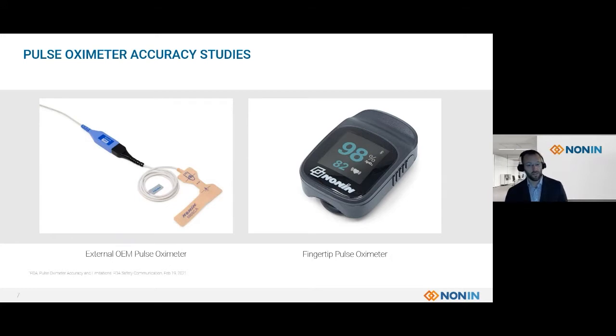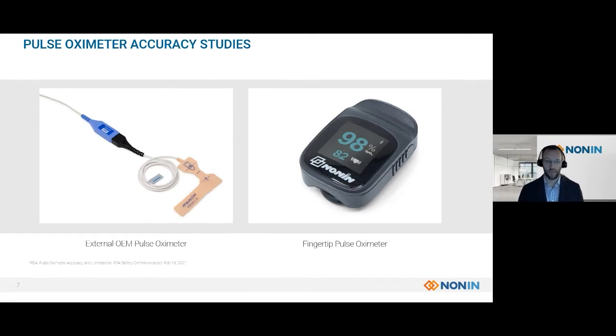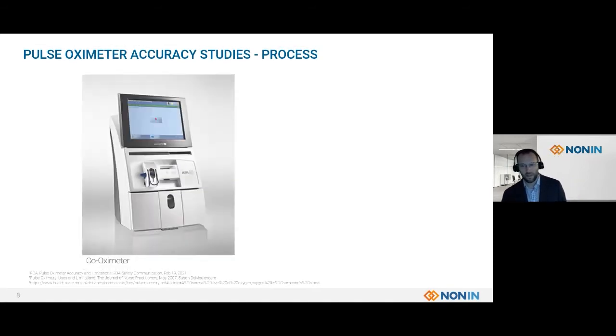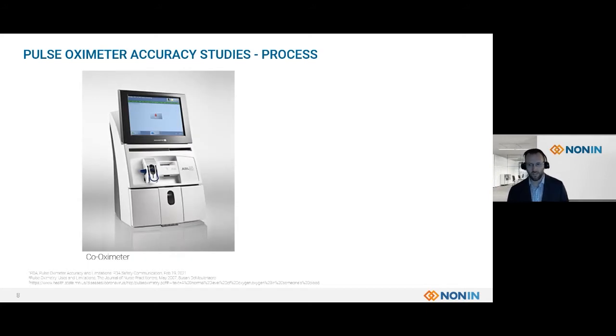These are the two types of our pulse oximeters, and both of these have gone through the same level of testing. So let's see about a pulse oximetry study. The true gold standard of saturation is actually measured by a co-oximeter, or also a blood gas analyzer. This is a picture of a very standard co-oximeter, and this is where we're getting the truth from. Our pulse oximeters are calibrated against the invasive blood gas machine to determine accuracy to standards and regulation claims.